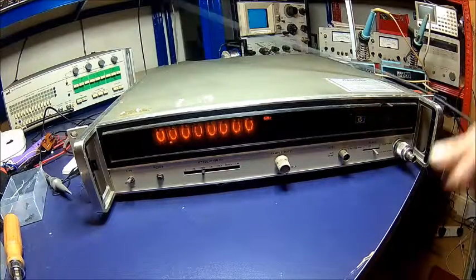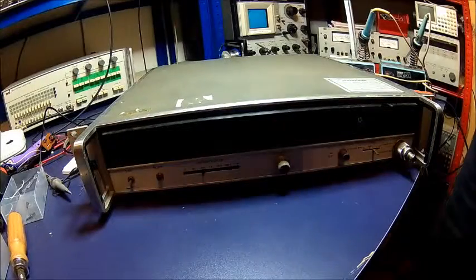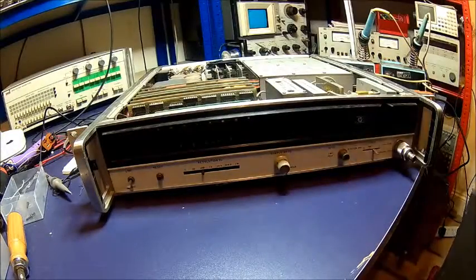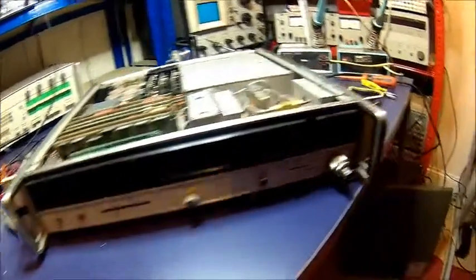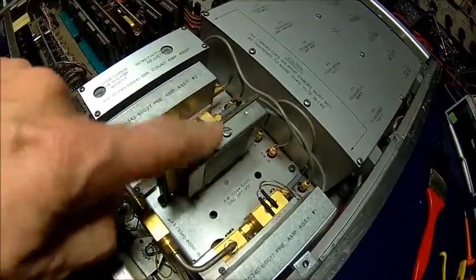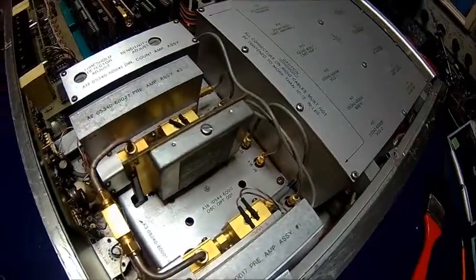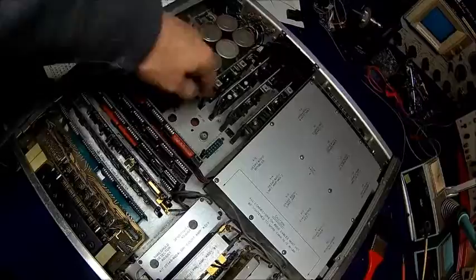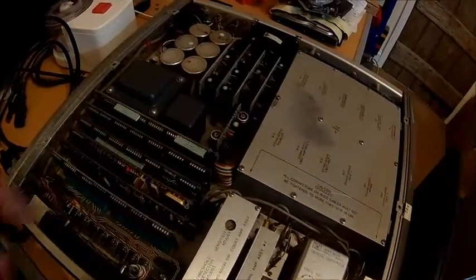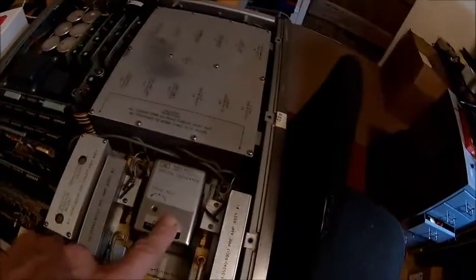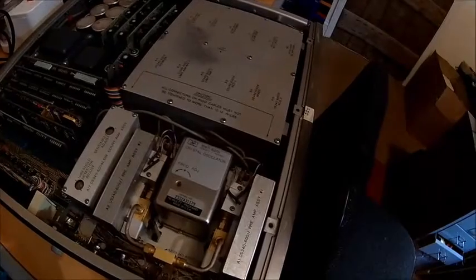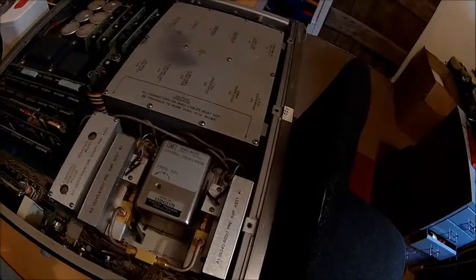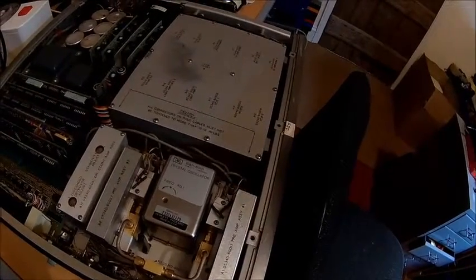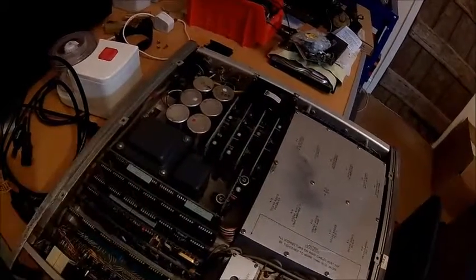Generator off here. Power off. So as we can see here, this one has the standard Timebase, and also the transformer is missing for the heated Timebase, as opposed to here, darker, sorry. There is a transformer here which permanently feeds the Timebase with power to keep that warm. So the job will be replacing this transformer, because this has died.